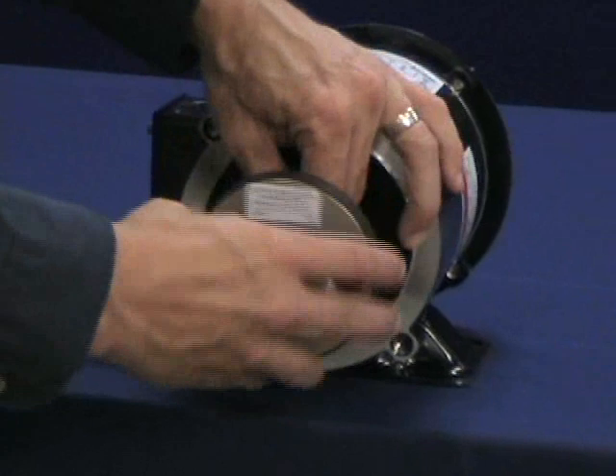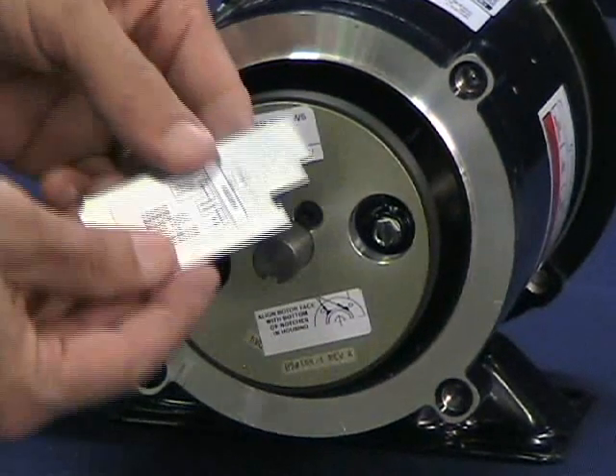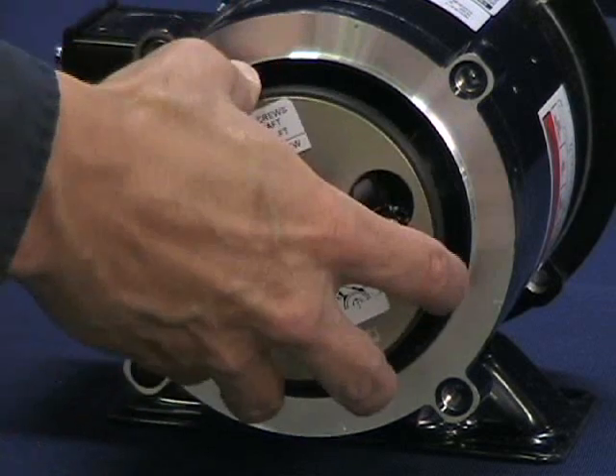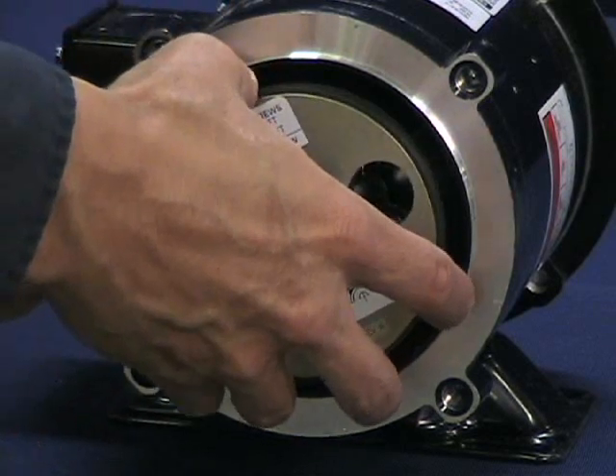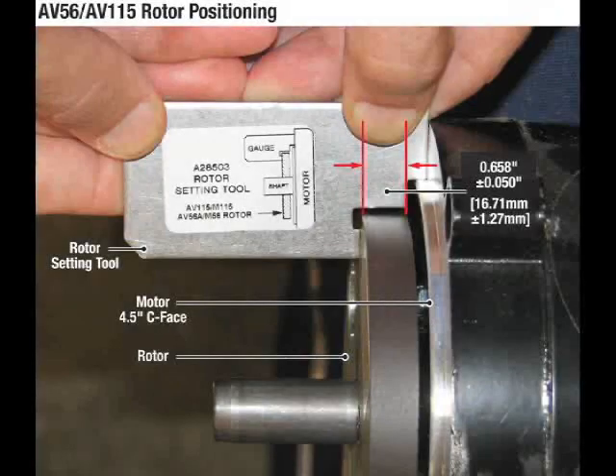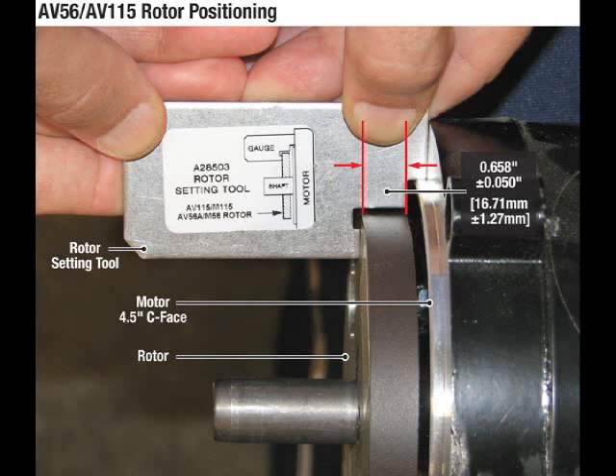Bottoming out the screws or backing them out excessively can lead to insufficient shaft holding force. Slide the rotor onto the shaft. Ensure the cam screws face away from the motor. The rotor must be properly located from the motor face. Use the rotor locating gauge and slide the rotor onto the shaft until it is in the proper position. The AV56 and 115s have different offsets from the C face. If a gauge is not available, use the housing as the gauge — this alignment method is shown later in this video.